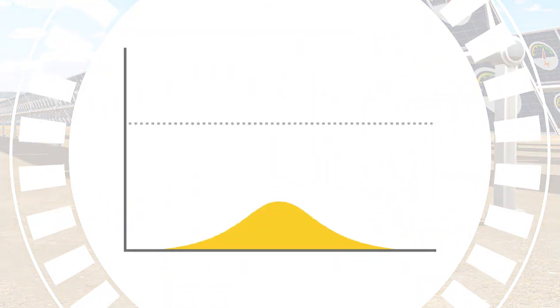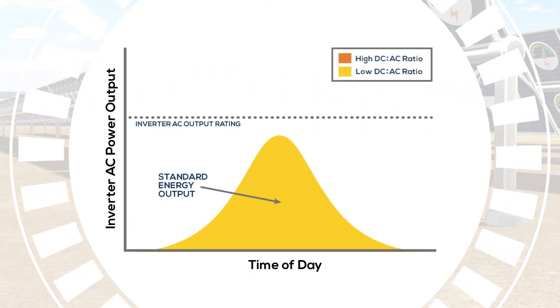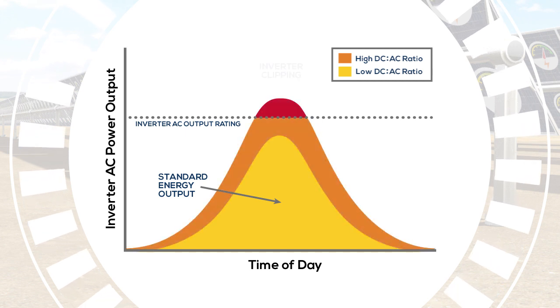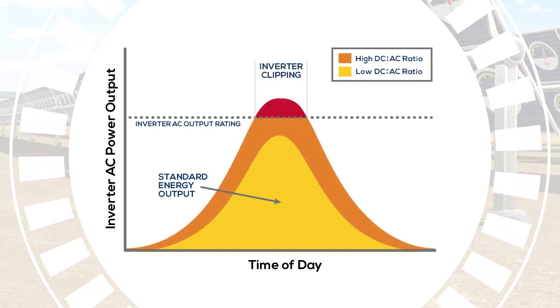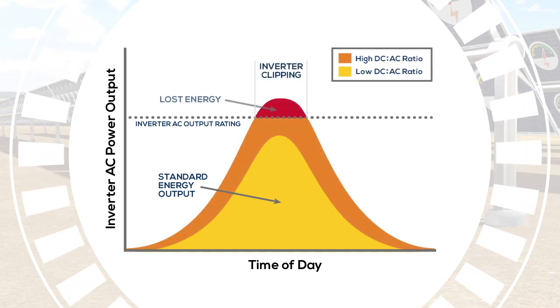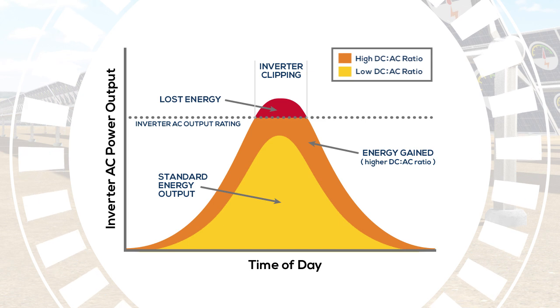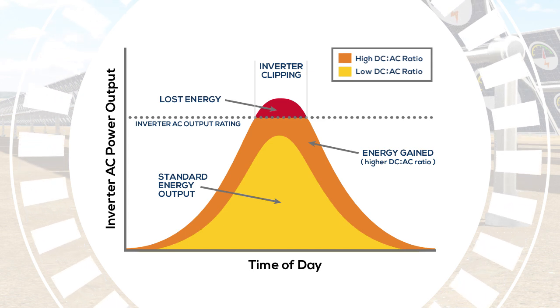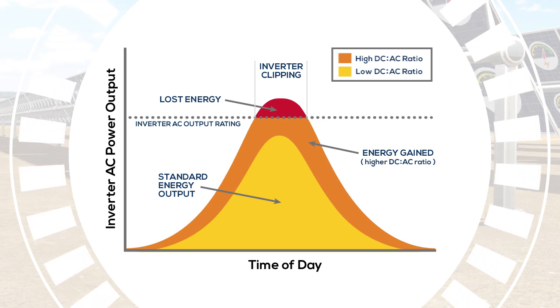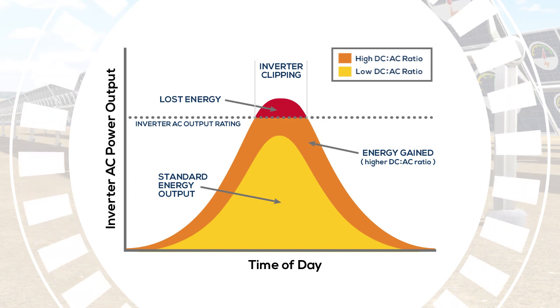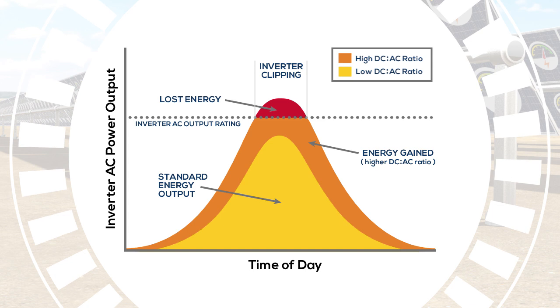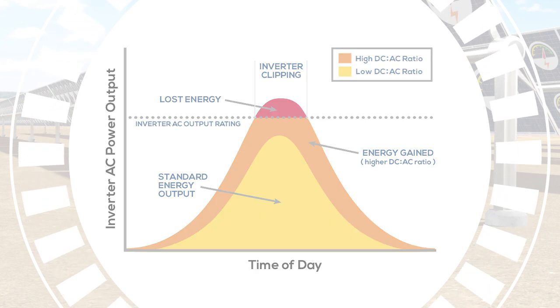Higher DC to AC ratios allow the system designer to widen production shoulders and to produce more energy for a given AC power line capacity limit. This is especially important where the PPA rate is high or there is a maximum AC power capacity limit in the transmission network.